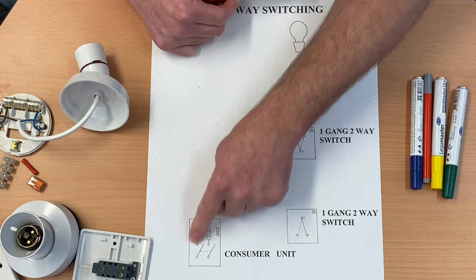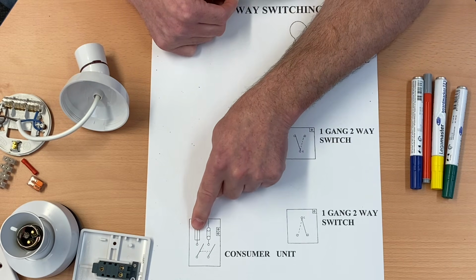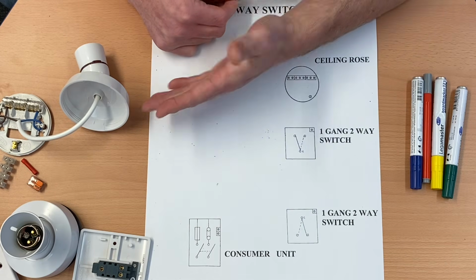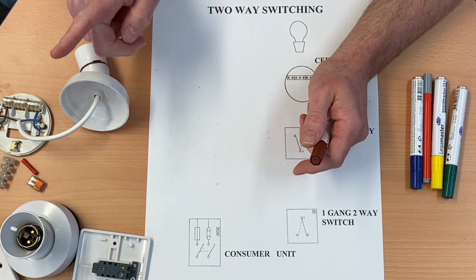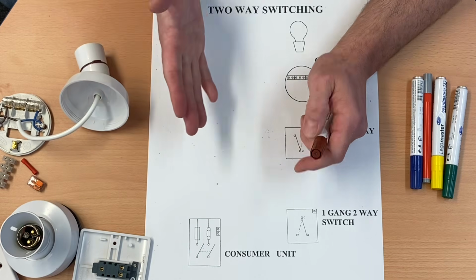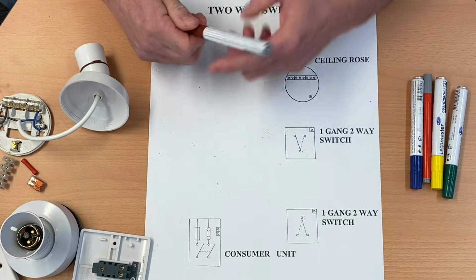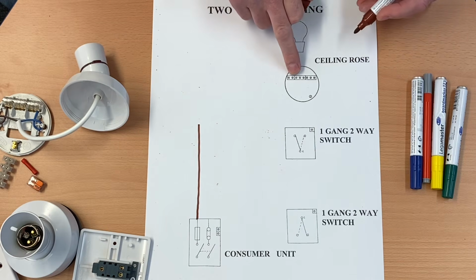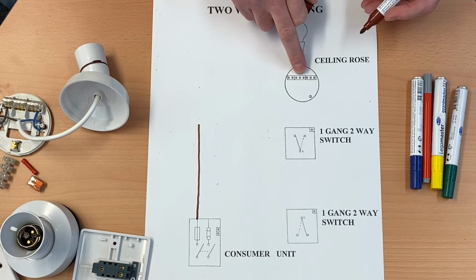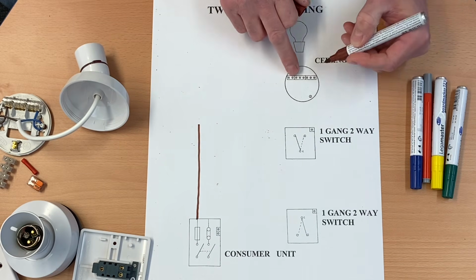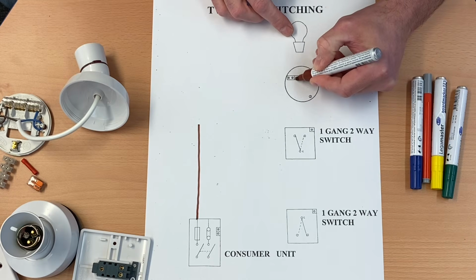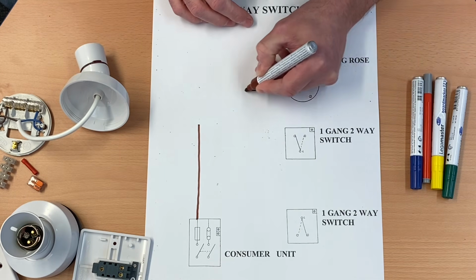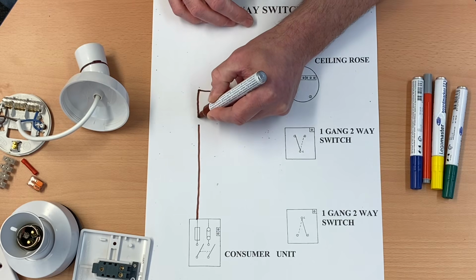We'll start off with a line connection here. For us, it's coming out of the consumer unit, so out the top of the circuit breaker. It could be, and we talked about this in a previous video, coming from the next room. It's still going to bring in the same connections. So we're going to bring in our permanent line connection, and we're going to use any of the three here in the center loop. To make it easier for my drawing, I'm actually going to use this one here on the end, so I'm going to pull that one down, and then we're going to bring the two together. Remember, I'm doing this freehand. I expect you to use a ruler.